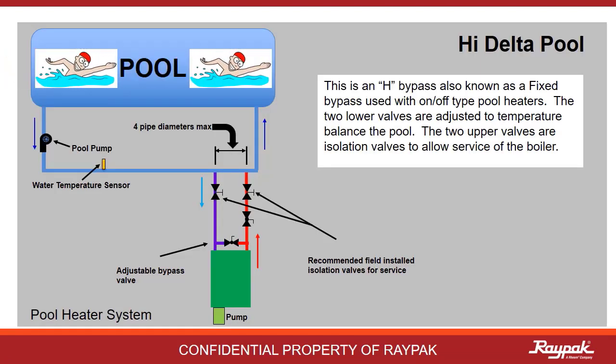As with the water heater type, if it is a pool heater, there is only one mode of operation. Here the decoupler is the distance between the supply and the return of the recirculation loop. The two upper valves are there to isolate the heater for service, while the two lower valves are there for temperature regulation.